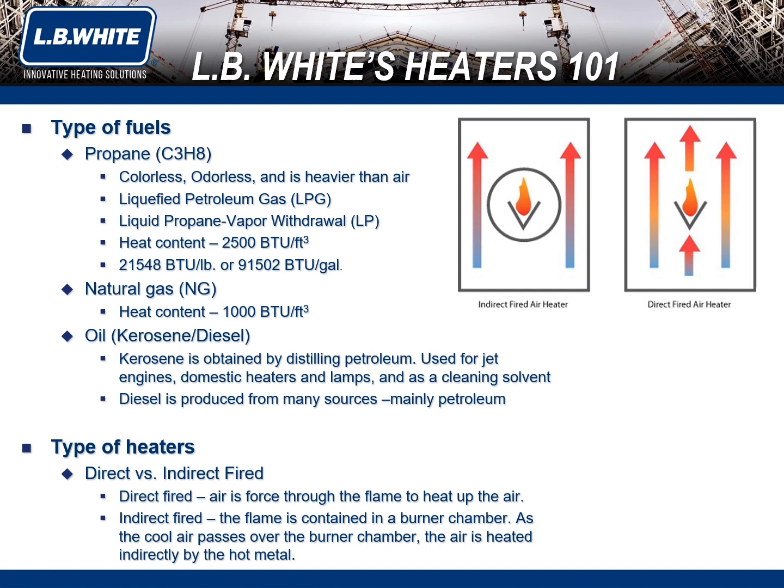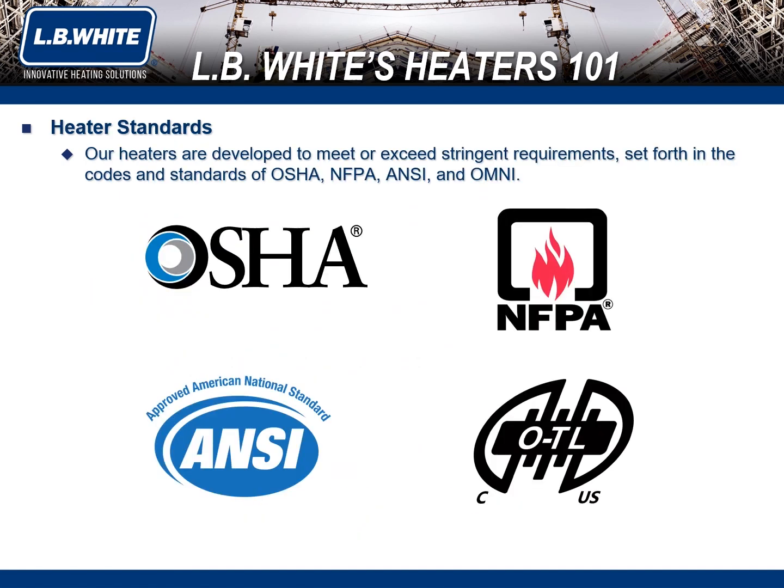The byproducts are then exhausted through the chimney, so you can just have warm, dry, clean air. Indirect fired heaters are about 80 to 95% fuel efficient, since about 5 to 20% of that heat is going out the chimney along with the byproducts of combustion, which can be poisonous. And lastly, our heaters are developed to meet or exceed stringent requirements set forth in the codes and standards of OSHA, NFPA, ANSI, and OMNI.